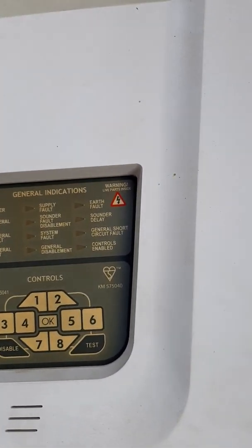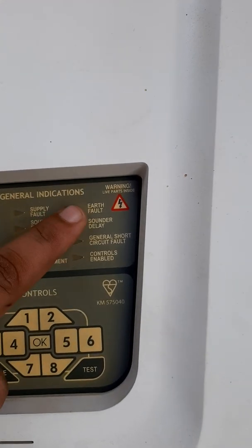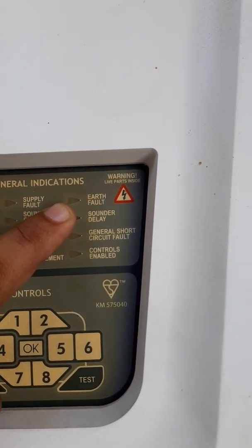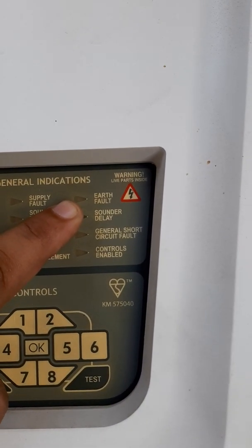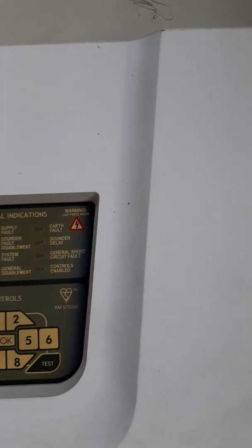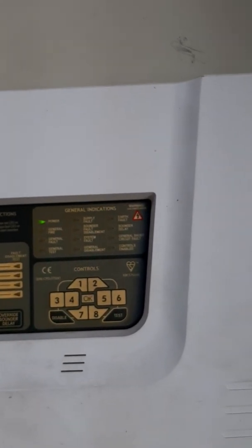The fourth fault is earth fault. If the earth fault indicator light is on, you check the negative wire and positive wire — maybe the negative wire or positive wire is touching the metal body.